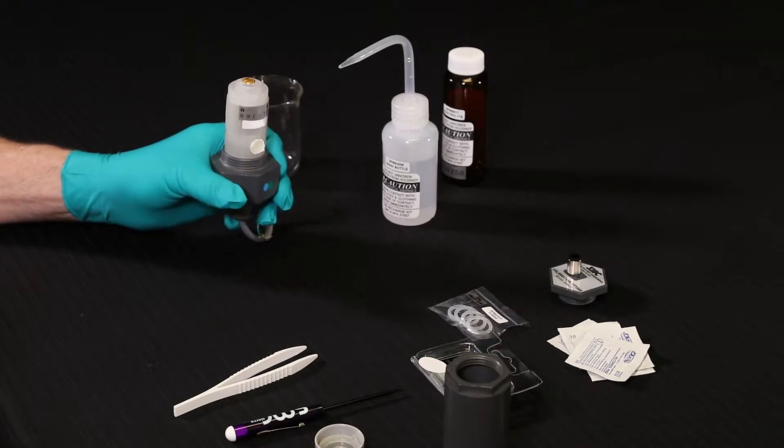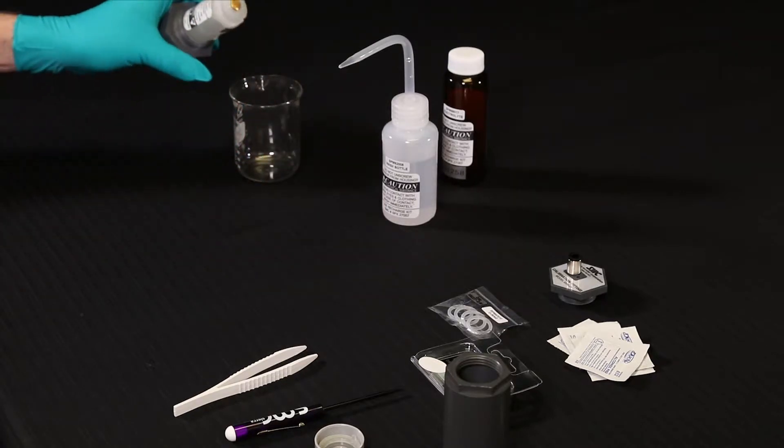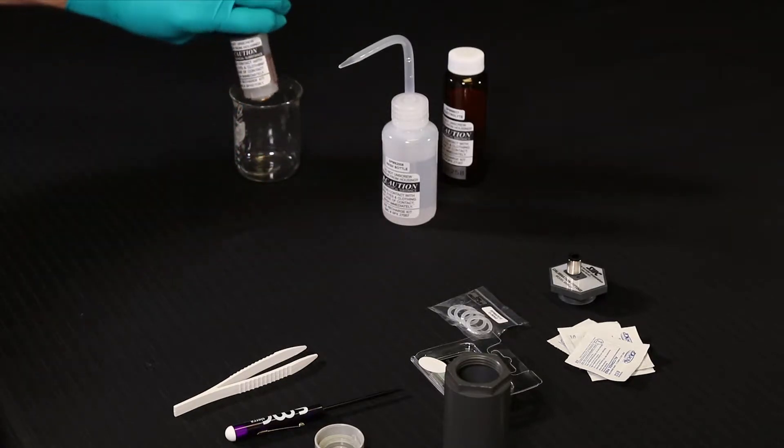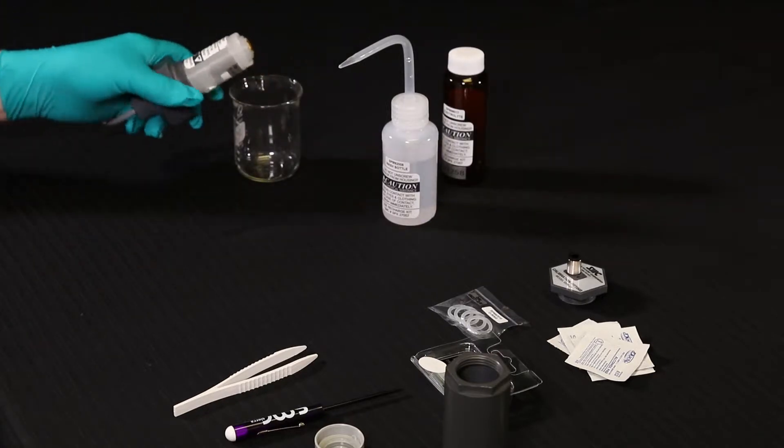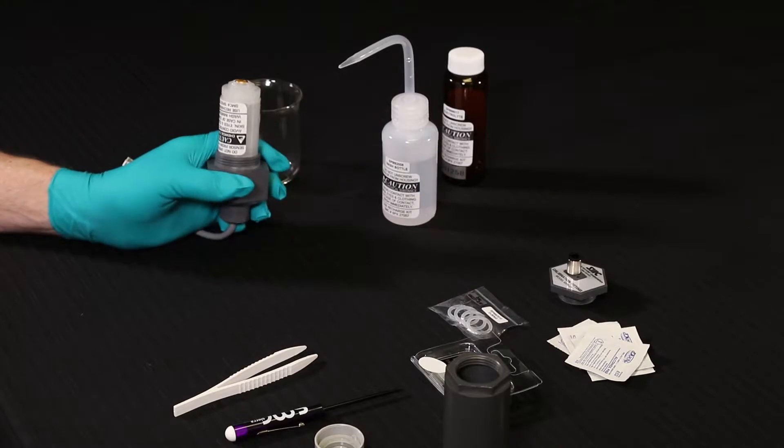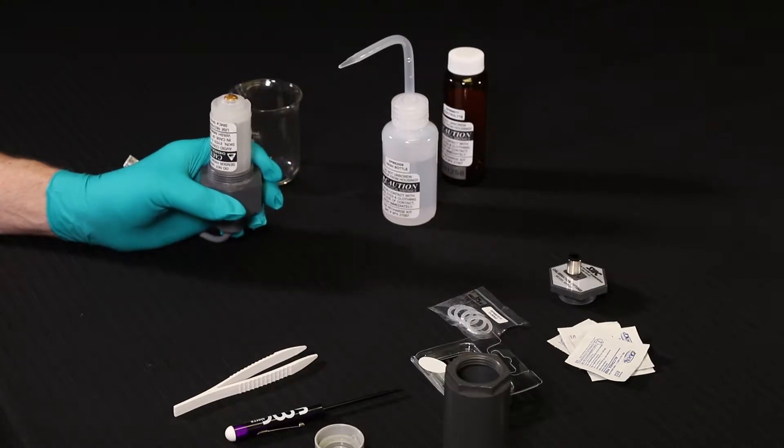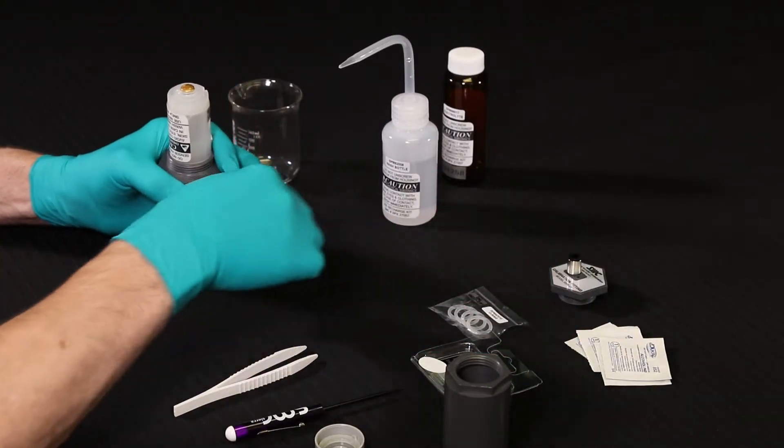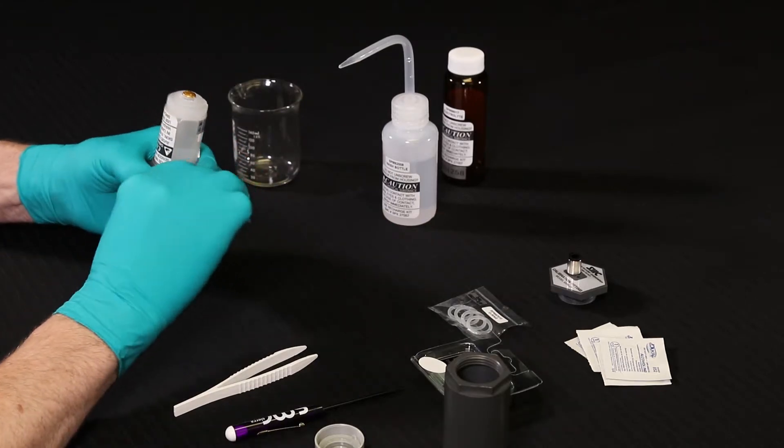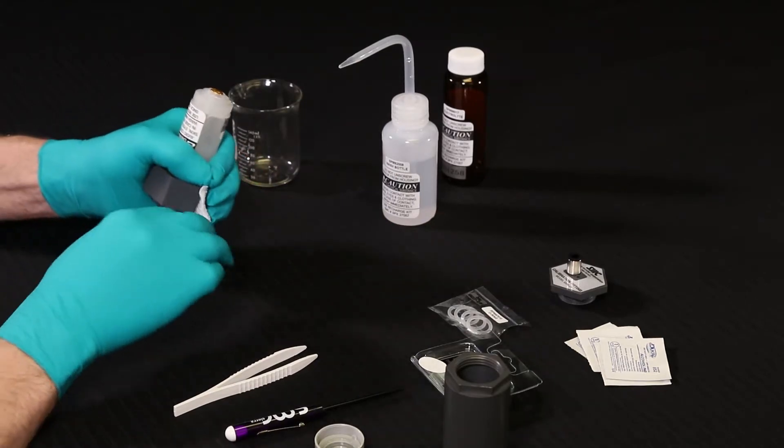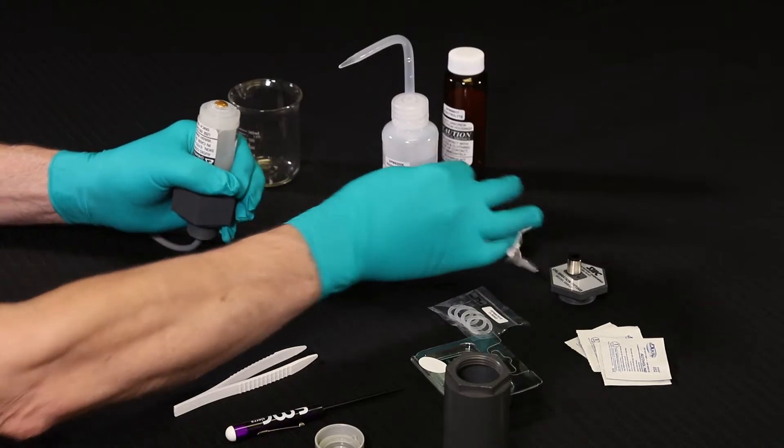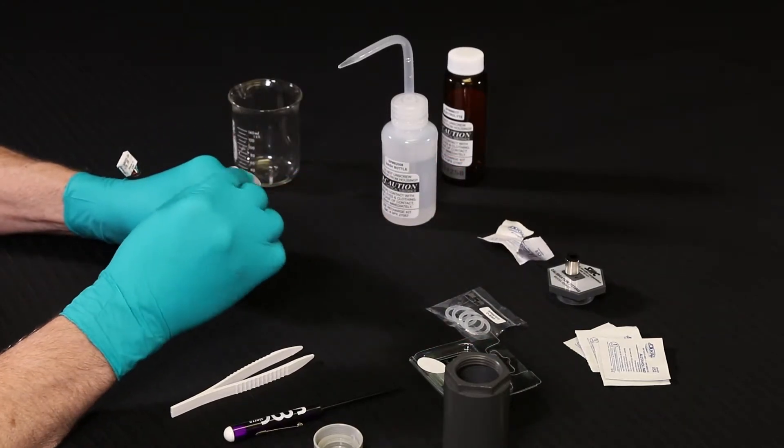Next, pour out the old electrolyte into the container for disposal. Next, use the alcohol swab to clean the electrode tip. Be aware that the tip may be discolored due to oxidation. Continue to scrub. The electrode tip must be clean and shiny.